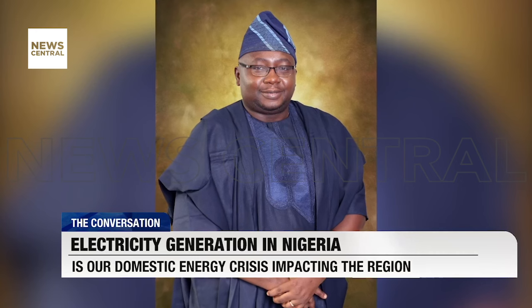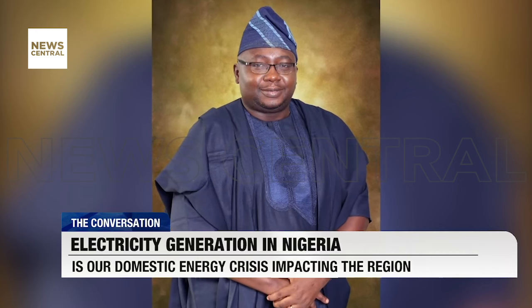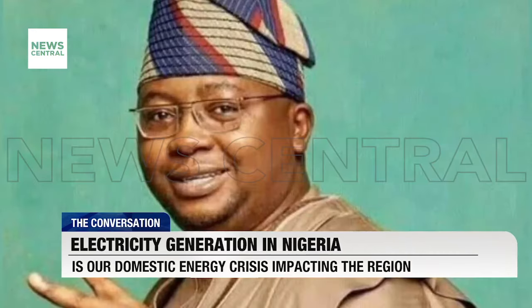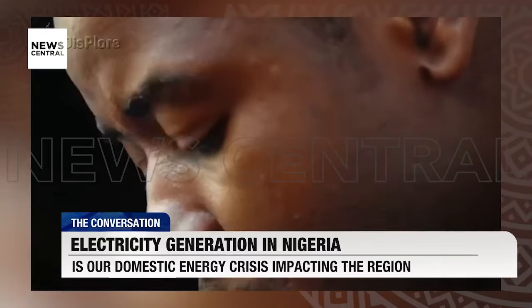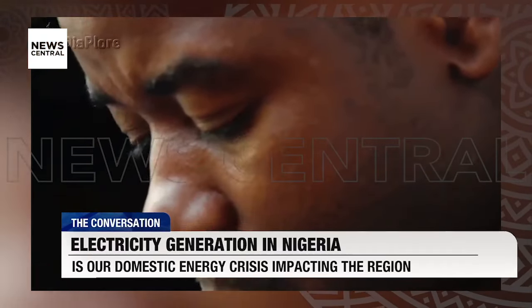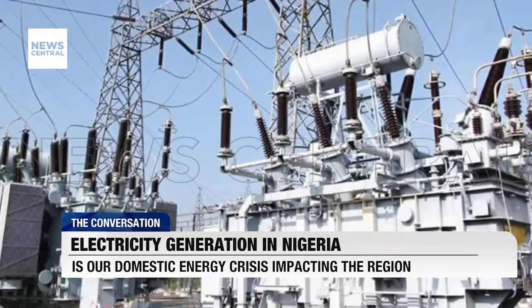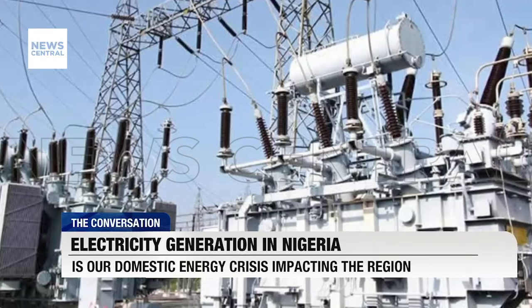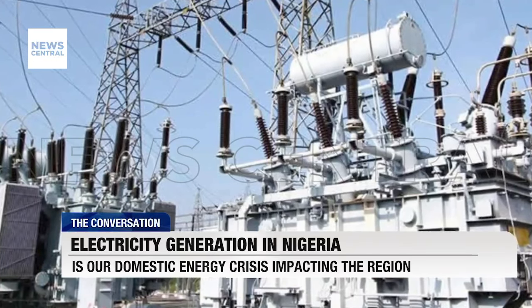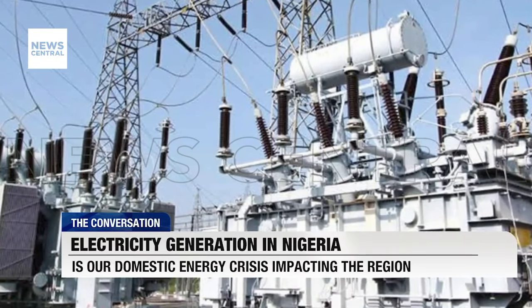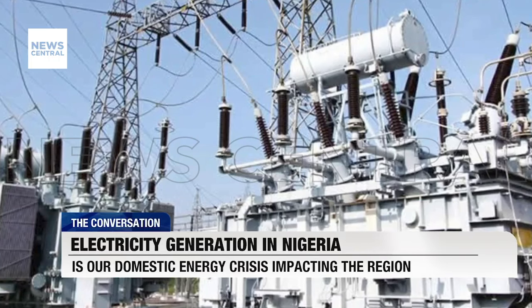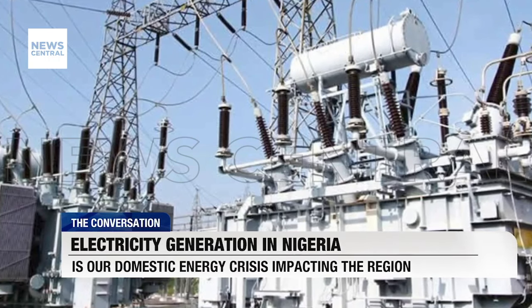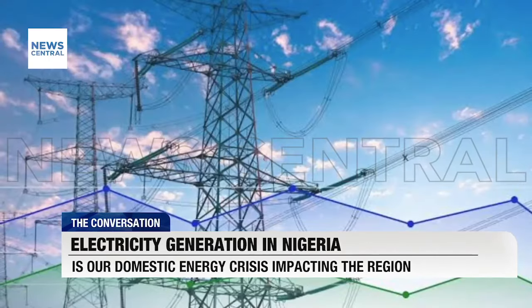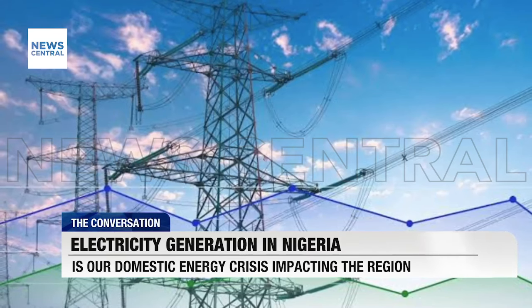Why? What happened there was a bus bar fault, as we will call it. There was a current transformer that blew up. But in a properly coordinated protection system, only one bus bar will be affected. The remainder will never be affected if that system was properly designed and the protection settings have been properly implemented.